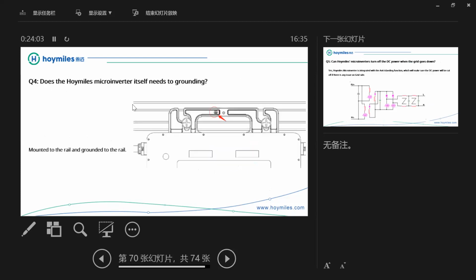Does the Hoymiles microinverter itself need to be grounded? Actually, there is a ground line in our AC cable, so it's not necessary, but some countries request our microinverter to be grounded on the rail. So you can see these pictures. You can use the screw to mount the microinverters to the rail.